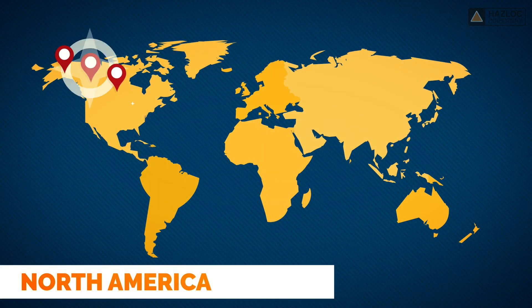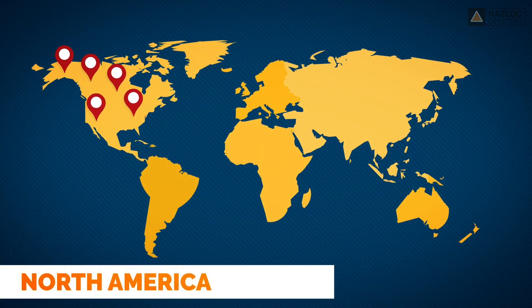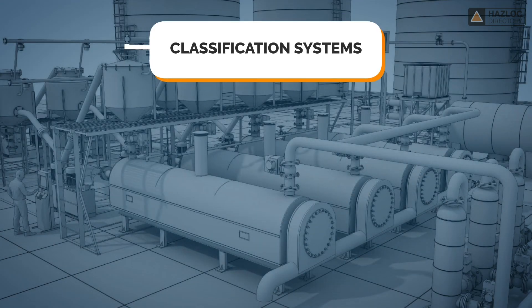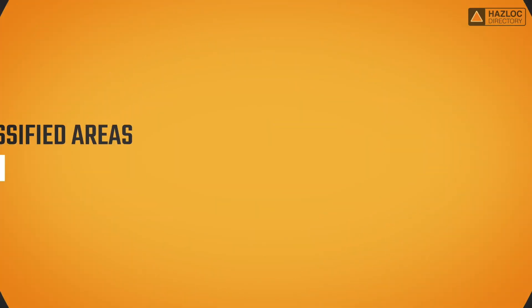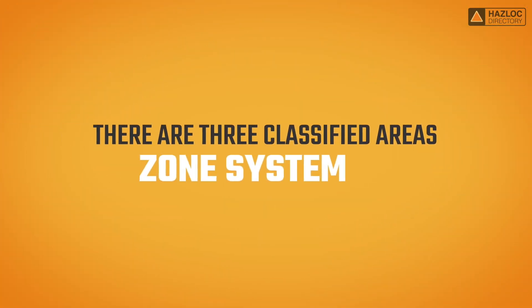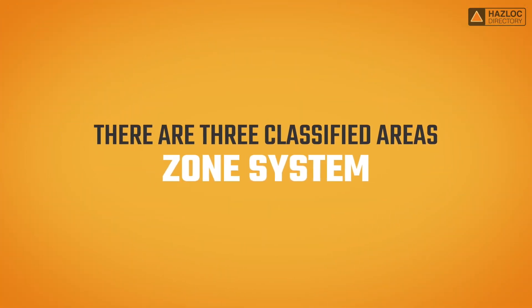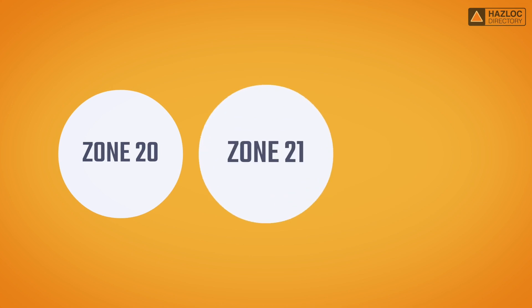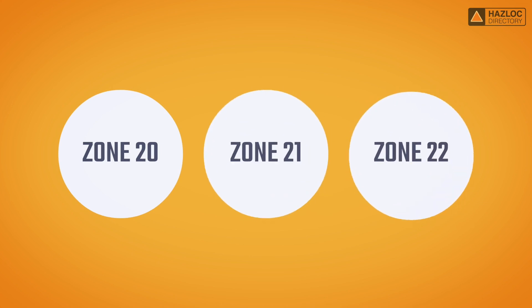Dust explosive atmospheres are classified in North America using two different classification systems: the class and division system and the zone system. There are three classified areas in the zone system that relate to dust explosive areas: Zone 20, 21, and 22.